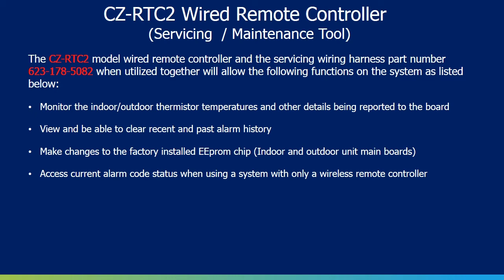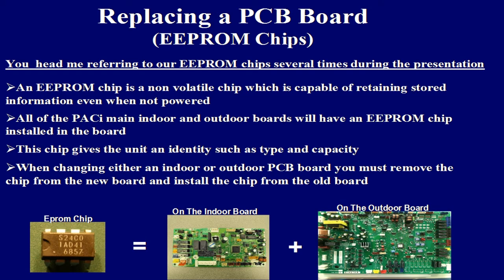When replacing either the main control board on the indoor or outdoor units, make sure the factory installed EEPROM chip is removed from the old board and transferred over into the new replacement board. This chip is also directional and has a defined marking on one side of the chip as illustrated in this slide. Use care when removing or installing the EEPROM chip, as the pins can be broken or bent.